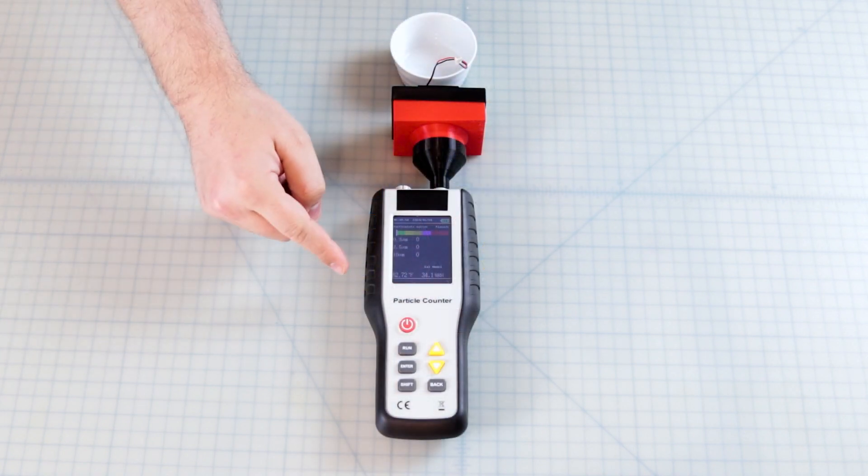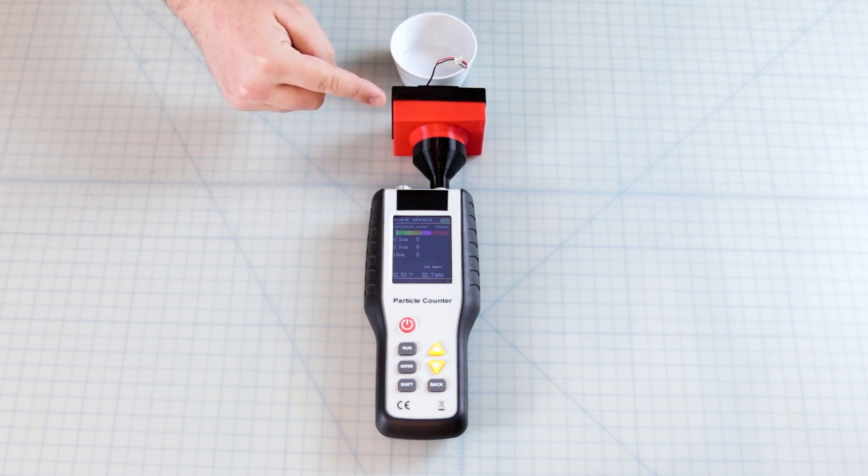Here's the testing setup: particle counter, an adapter, the filter cassette, a fan to push air into the filter, and a small container to spray an aerosol.